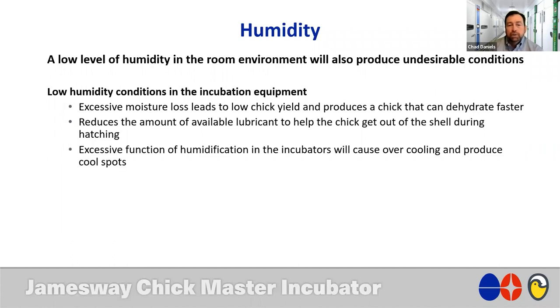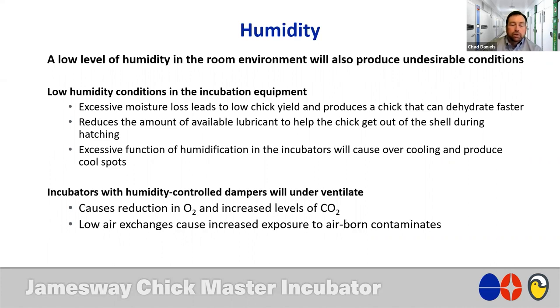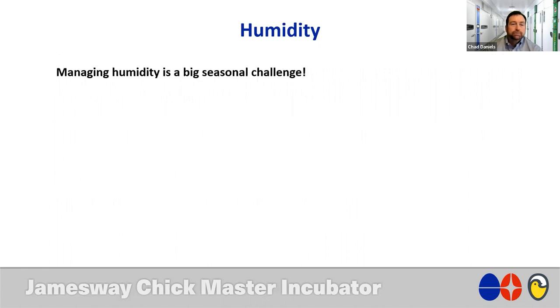Excessive function of humidification in the incubators can cause overcooling and produce cool spots. And then incubators with humidity control dampers will underventilate. That's going to cause a reduction in our vital nutrient, oxygen, and it's also going to cause increased levels of CO2, and generally at a time when we don't need it. So also we'll have low air exchanges, which causes increased exposure to airborne contaminants.